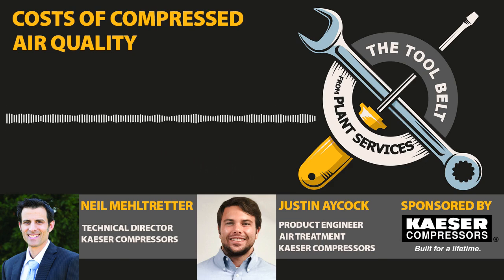So every use that's out there, if it's unregulated, is going to use more air if you're running at a higher pressure. So if I was able to run the entire plant at, say, 90 pounds, I'm going to have a significant savings running at 90 pounds than I would at 100. And that's that artificial demand. The interesting thing with artificial demand is that all your tools may seem like, let's say you have an impact, my impact runs better at 120 pounds. Well, it will, but it's not going to run as long as it would if you were running at 90 pounds. So, the longevity of the tools, you're going to have to replace those pieces of equipment faster. So those are some other hidden costs that you might have.